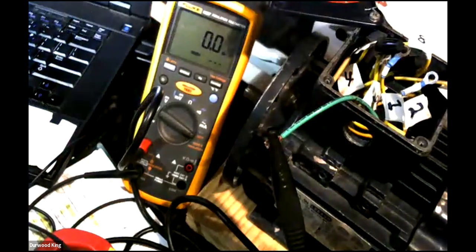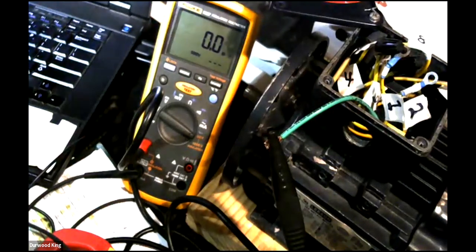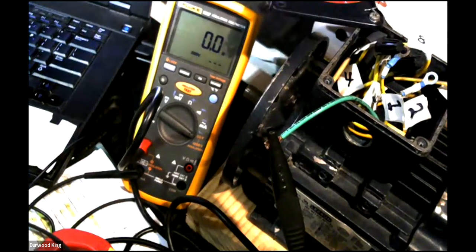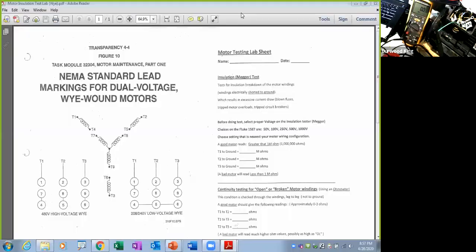So the way that you, if you look closely, look back on your screen here, what you're talking about, Victor, is this. So let's go back to a screen share. Go back to your screen share and look at here. When you put your ohm meter between T1 and T2, you're going to read through the windings and you're going to get a reading, okay? You're going to actually read the resistance of those 4 windings in series. If you read from 1 to 2 or 1 to 3, you're going to read through that set of windings. If you read from 2 to 3, you're going to read through those windings.